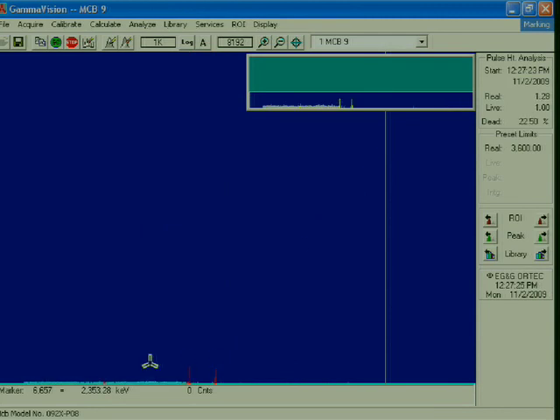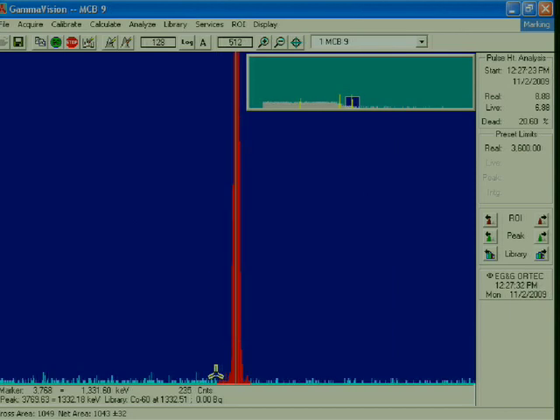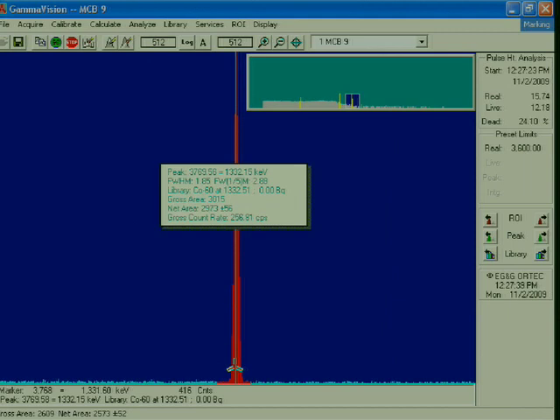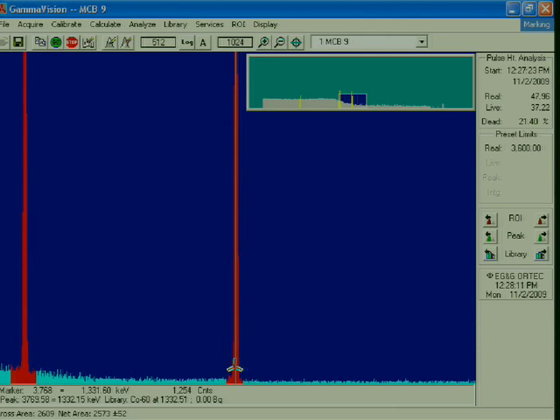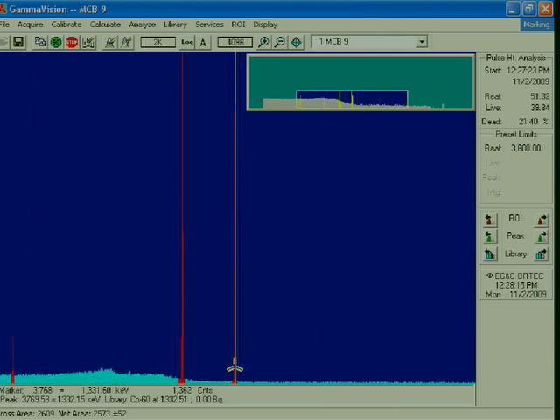And so now, if we go back, let's look at the 1332 keV peak. So it's counting nice and fast, and if I ask it to fit it, what it's done now is it's fit this to a shape. The typical shape in a detector like this is what's called Gaussian, and it figures out that the full width at half maximum is 1.8 keV. So for an energy of 1332 keV, the energy resolution is 1.8 keV. It's about 0.15% in percentage terms. Okay, so it's much, much better than that sodium iodide detector and infinitely better than the plastic scintillators.